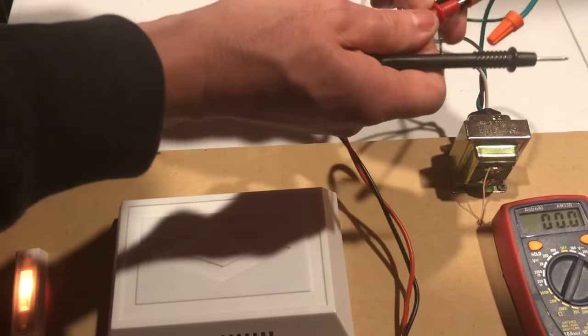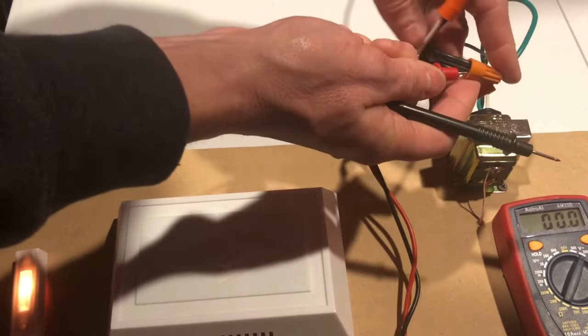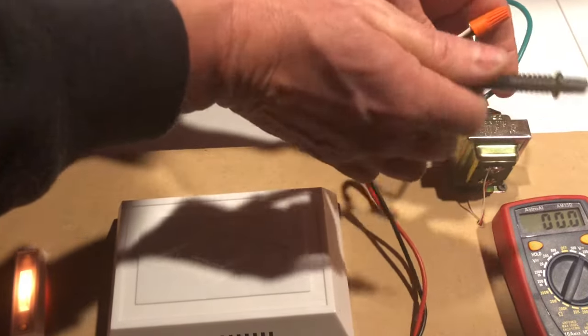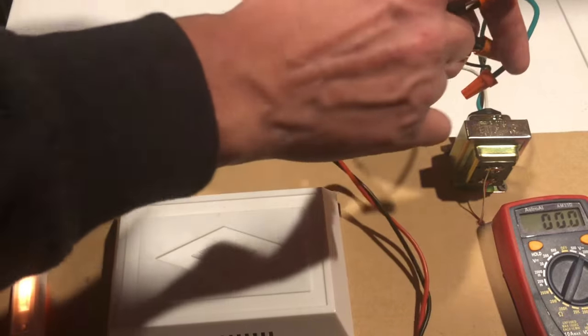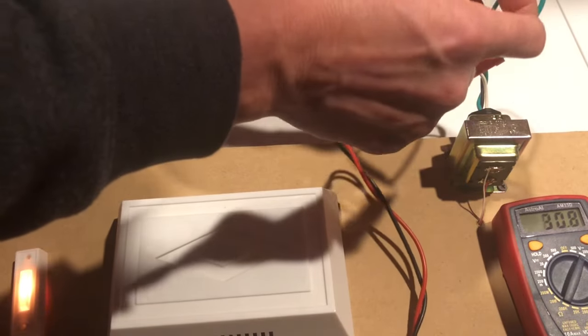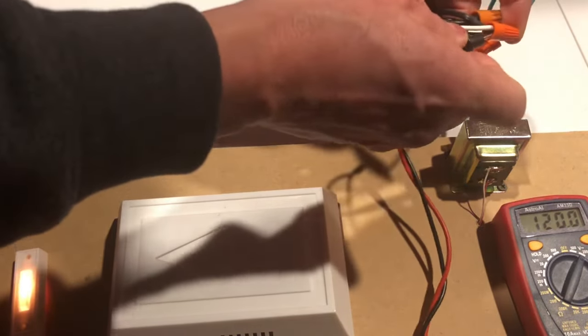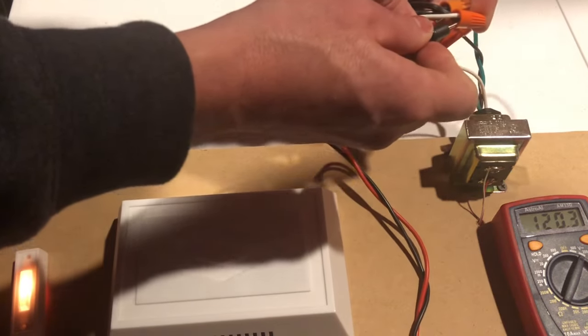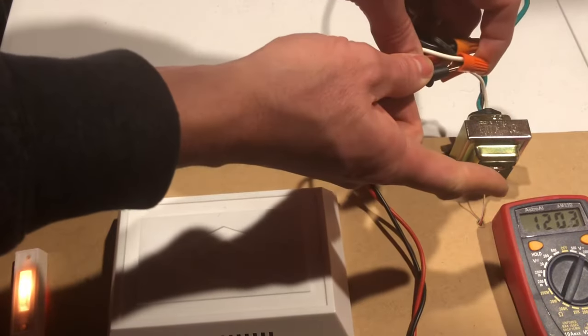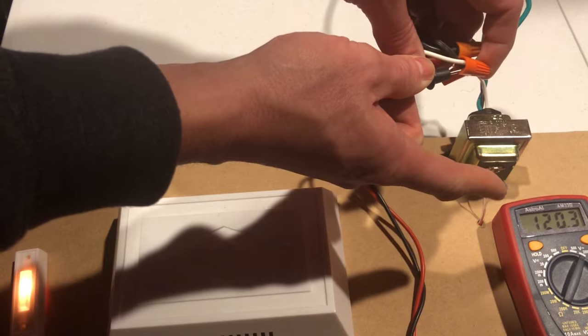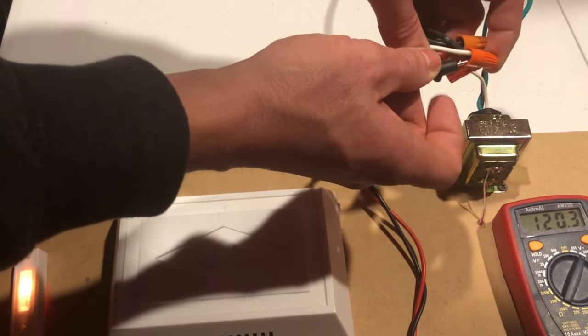And you have to make sure that you fully pressed it up there and it's making good contact. Else you're not going to get a voltage on it. So same with the white one, I'm going to stick the other probe in the white. And now I'm testing both. So we can see that we're getting 120 volts to the transformer. So if this was reading zero...